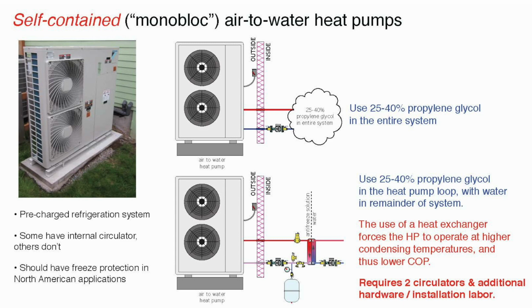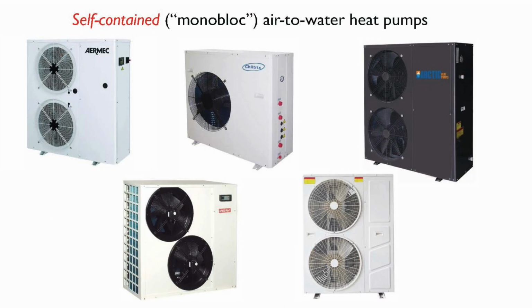With the heat exchanger, you're inducing a performance penalty on the heat pump. You're forcing the heat pump to run several degrees warmer than it would have to run if the heat exchanger wasn't there. You have to do that to drive the heat through the heat exchanger. Either one's possible, but in general, the better performance is going to be where you don't have the heat exchanger. Again, there's several samples here to take a look at.